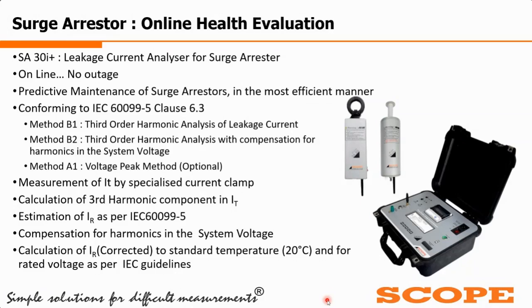Method B1, as I have shown you in the chart two slides back, is available in the kit. That is third harmonic analysis of leakage current, only third harmonic analysis. Method B2 is where we do the third harmonic analysis with compensation for harmonics in the system voltage. So system third harmonic measurement with system harmonic compensation is method B2. For that one, we require this field probe. And for the third harmonic leakage current measurement, we require this CT, a specially designed clamp-on meter.